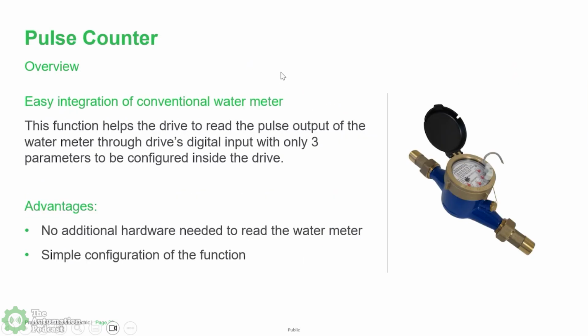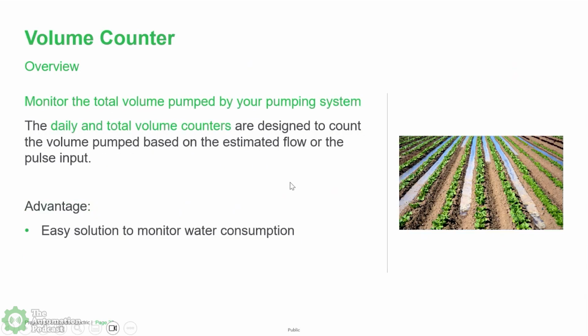But if you somehow do need to be very precise, the VFD can read a pulse counter and be very precise about how much water we're flowing, and even use that for invoicing or measuring purposes. So this is another way we can use a volume counter. A volume counter would either read from the VFD flow estimation or from the pulse counter and let you know how much daily or total volume flow you're getting, based on the reset that you program onto the VFD.